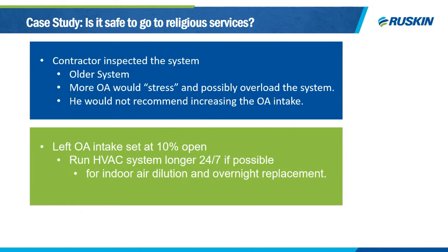A fixed outside air damper is often closed in an older building to increase heating or cooling capacity during extremely hot or very cold days, and unfortunately, it's seldom returned to the correct position. Ideally, the amount of outside air coming into the space is measured and controlled based on the number of people in the building. However, if a system today is operating with a fixed outside air damper that's only 10% open and cannot be increased, then one of ASHRAE's strategies for the operation of the HVAC system, one method here to increase outside air ventilation, is to run the system longer, all day long, 24/7 if possible.